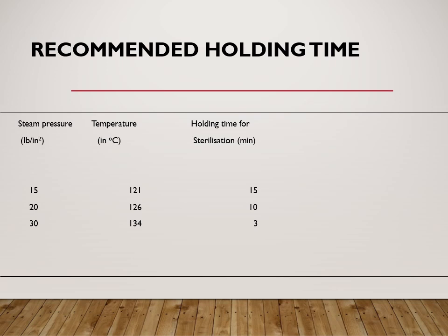Holding time is the time that starts once the required temperature and pressure for sterilization have been achieved. The most commonly used condition is 121 degrees Celsius at 15 psi steam pressure, maintained for 15 minutes. If temperature is raised to 126 degrees Celsius, the holding time is reduced; at 134 degrees Celsius, only 3 minutes is needed. However, 121°C at 15 psi for 15 minutes is the most commonly used standard.